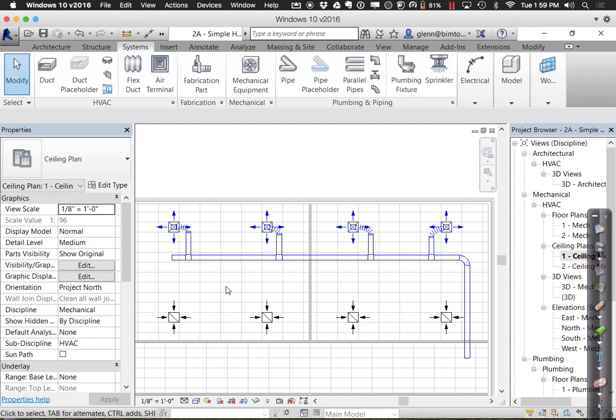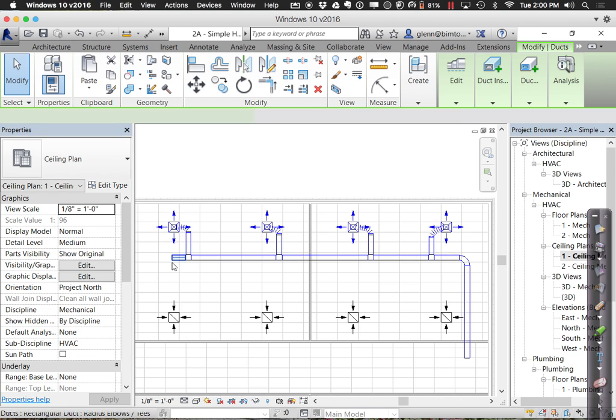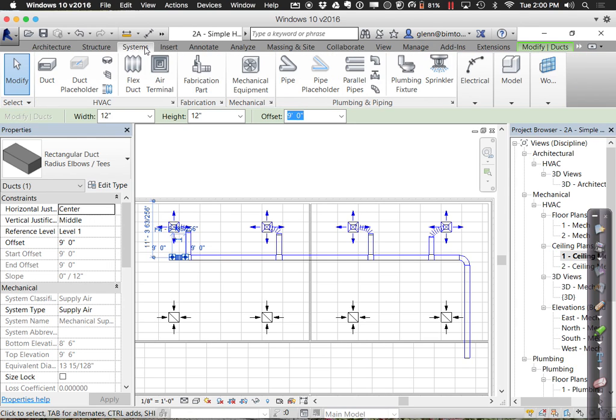If you want to start sizing these ducts, there's something called the System Inspector which lets you see the flow. The System Inspector is going to be your friend — when things start looking wrong and you don't understand the behavior, it will let you see what is currently calculated as going through each section. To use the System Inspector, we do have to cap one of the ends so it understands which direction the air is flowing. I'll choose the end segment and under Modify Ducts, there's a 'Cap Open Ends' option to seal it off.